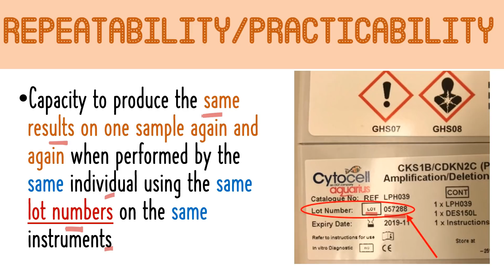Okay, so that method is said to be repeatable and practicable if you have run, okay, the same result, okay, paulit-ulit, okay, and using the same lot numbers on the reagent, okay, on the same instrument. Okay, so that is a good quality of your QC material or your reagent. So reproducibility, okay, is the capacity of the method to produce the same results on one sample again and again when performed by different individuals on different days using different sets of reagents.